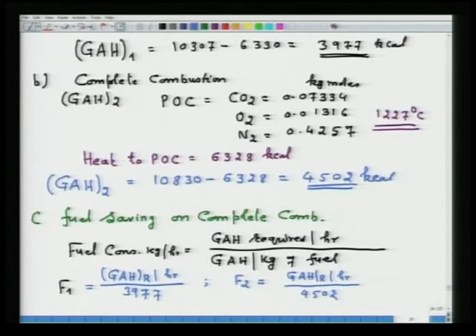So, I will put it as gross available heat required per hour upon, in the first case, 3977. We can calculate now F2, for complete combustion. So, the gross available heat required per hour divided by 4502.